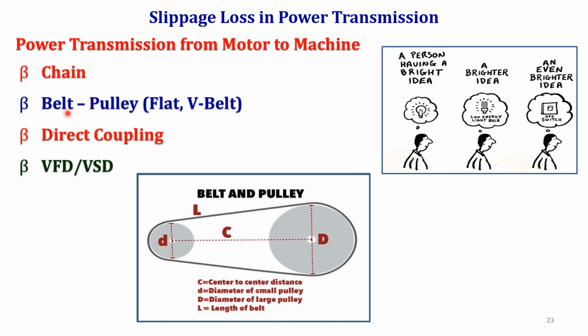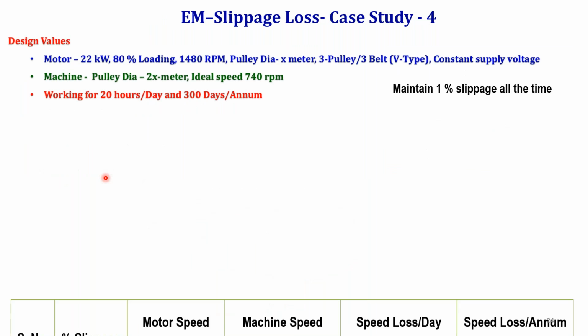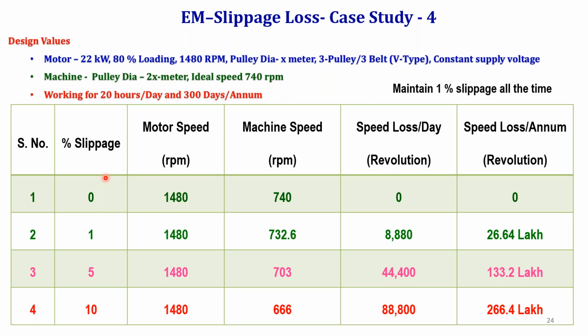It can be a chain, or a belt and pulley arrangement. Again, it can be a flat or V-belt pulley, or sometimes direct coupled. In AHUs and similar equipment, it is direct coupled. Nowadays direct coupling is available. Even sometimes AHU will have a VFD connected, and belt and pulley drive is also available. Then we have variable speed drive and variable frequency drive. Then a simple study will show you the slippage losses in the belt and pulley.